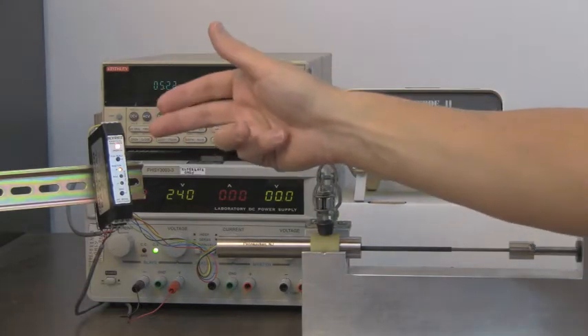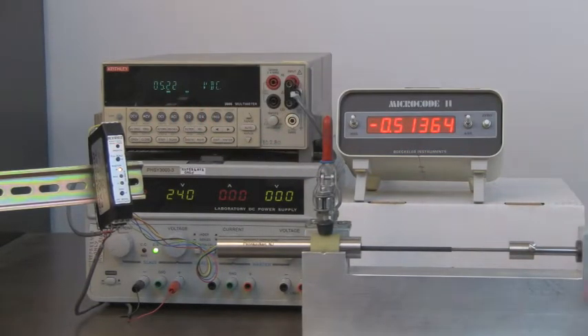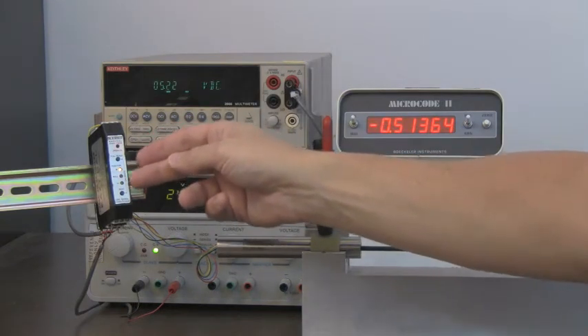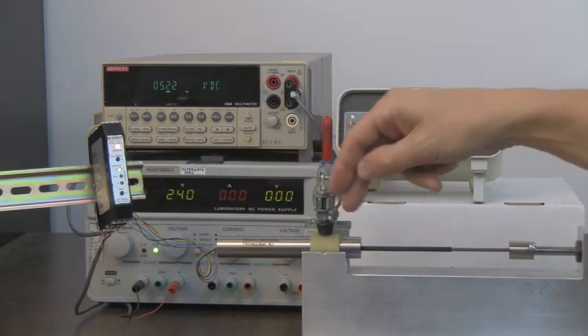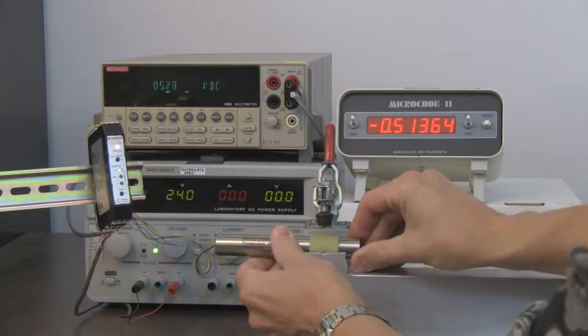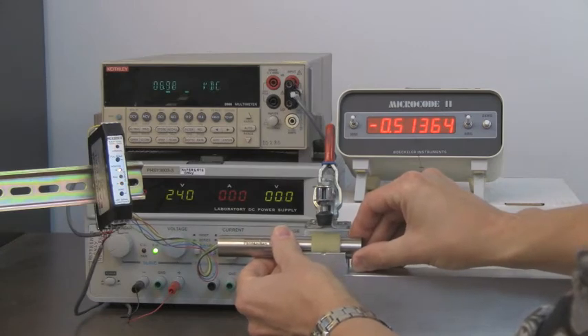Now that we have entered calibration mode, you will notice that the plus and minus LED lamps above and below the null LED indicator lamp will flash on and off as the LVDT coil is passed up and down the core. These lamps provide a visual position indication of the coil relative to the core.